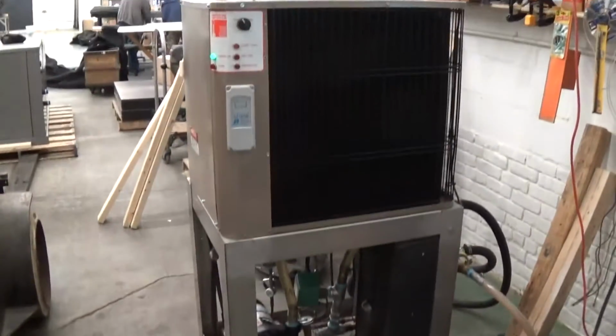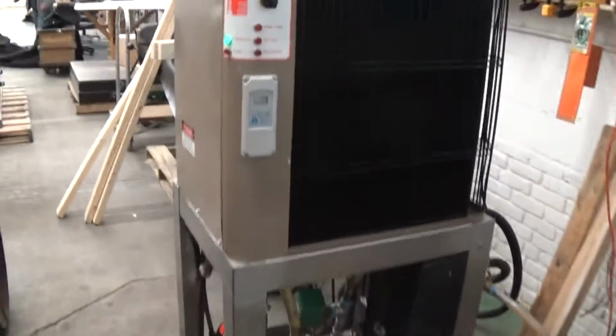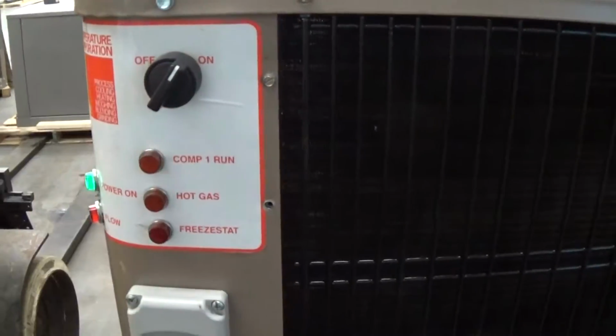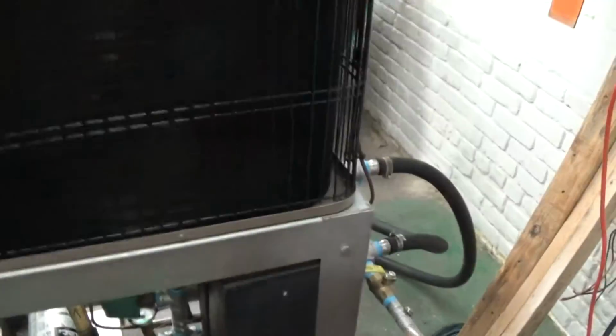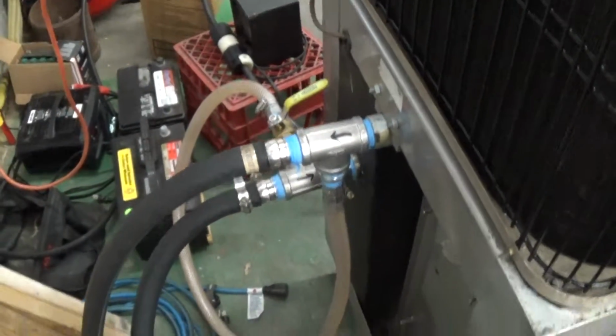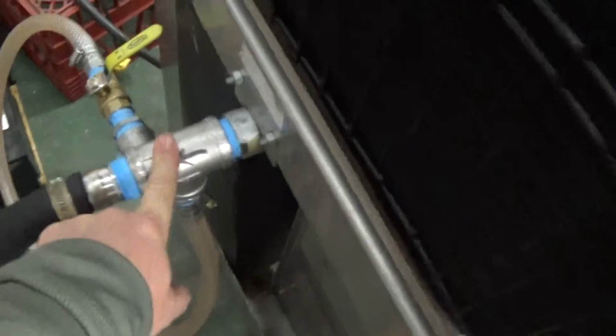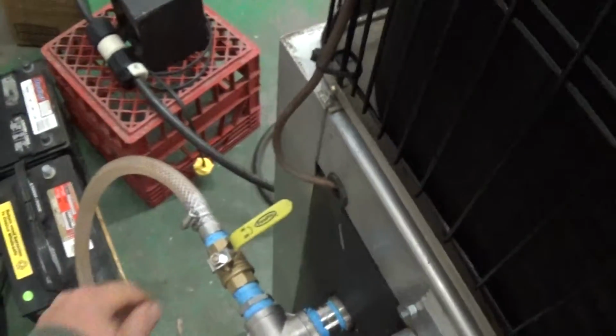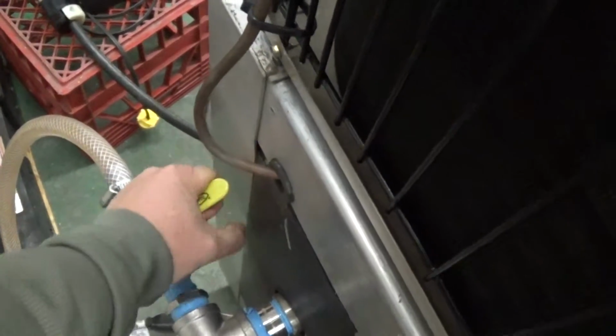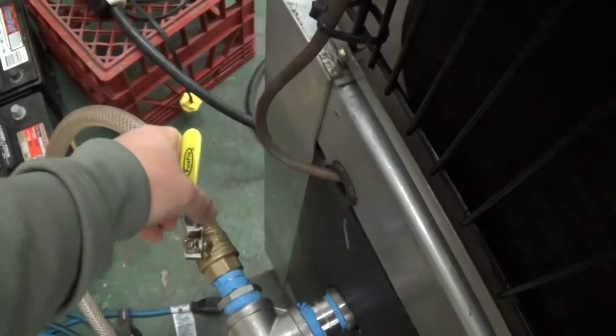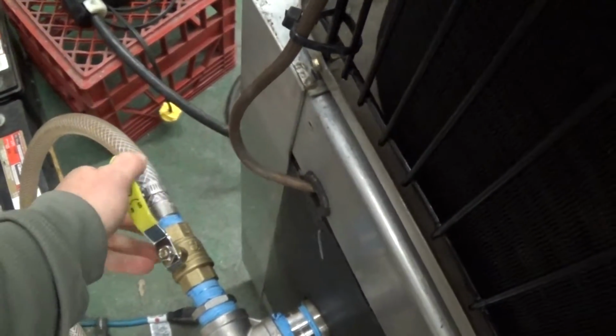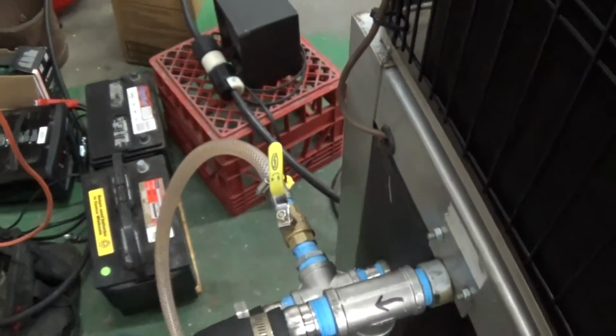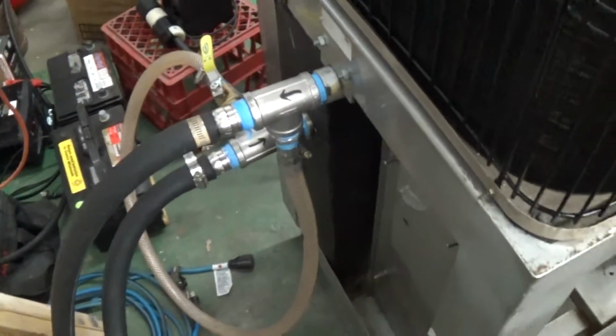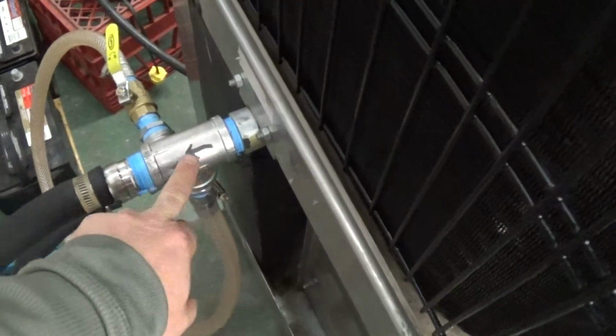So the first thing we're going to do here on this unit is come on over and turn our on button on here. Okay. Now this unit here, for this customer, we have a bypass because they might not need a whole lot of flow. We actually have this bypass here set up between the inlet and outlet. Right now I have it completely closed. That's completely open. Depending how much flow they need, it might be mostly open, but we'll see. And we have some nice stainless fittings here, and we labeled the outflow and the inlet flow with some arrows.